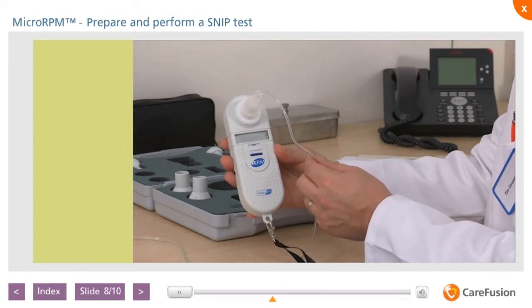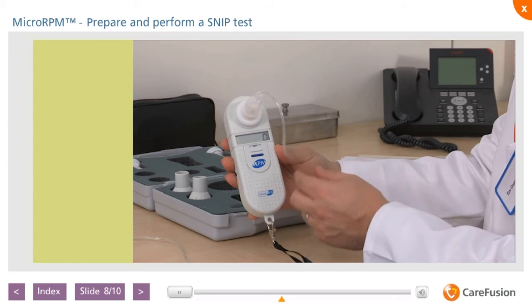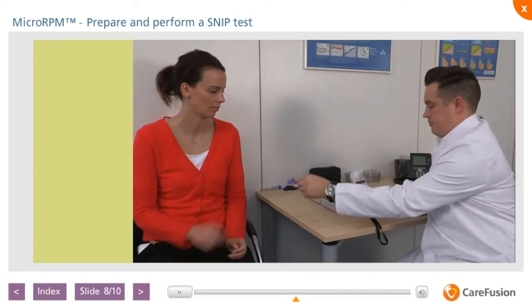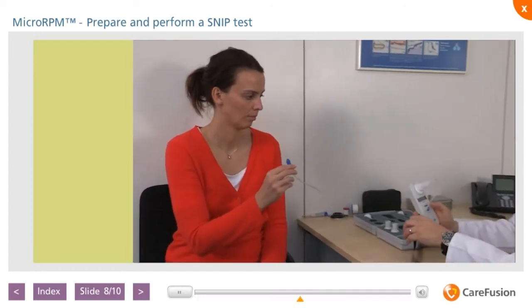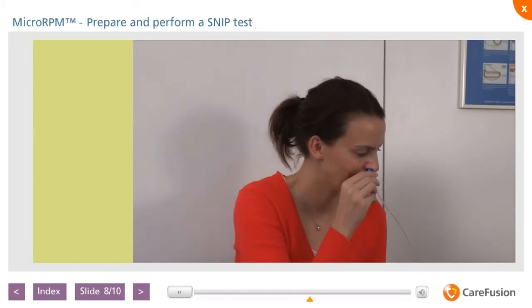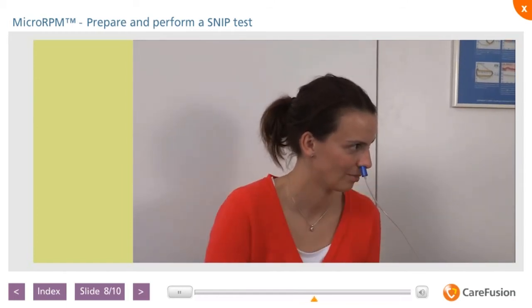after approximately 4 seconds, and the screen will display the digit 0. Whilst the unit is zeroing, it's important that no pressure is applied to any part of the nasal probe assembly. Sniff nasal inspiratory pressure measurements are performed at the end of a normal tidal breathing maneuver. The patient should place the nasal probe into her or his nostril so it fits tightly and won't fall out during the maneuver. The patient should be instructed to perform a short, sharp sniff through the nostril. The other nostril should remain open and shouldn't be occluded.